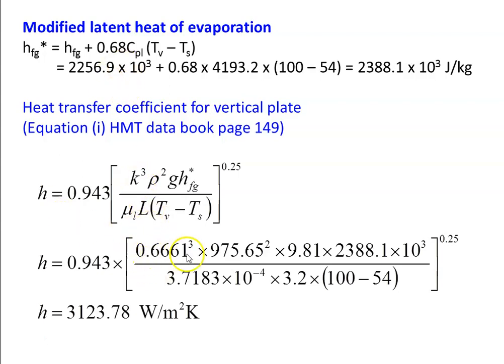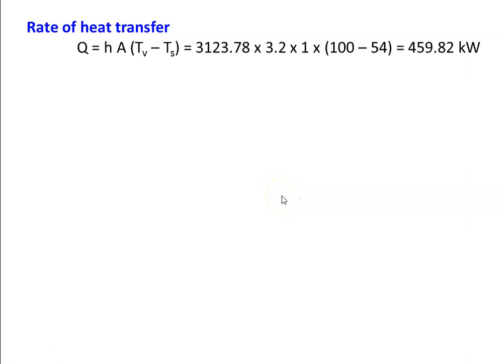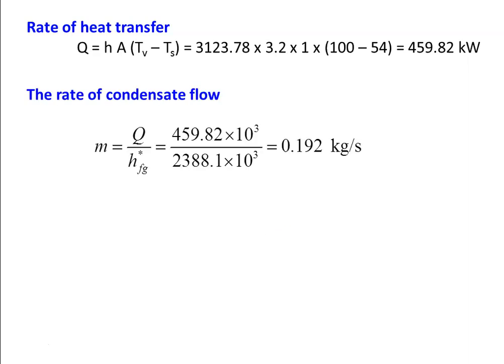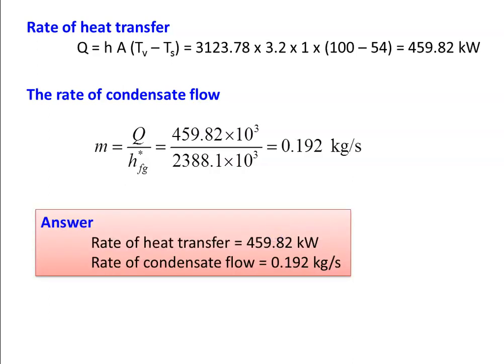Carefully check the substitution: K = 0.6661, ρ = 975.65, g = 9.81, HFG* = 2388.1 × 10³, μ = 3.7183 × 10⁻⁴, L = 3.2 m, and Tv − Ts = 100 − 54 = 46°C. The rate of heat transfer Q = H × A × (Tv − Ts) = 3123.78 × 3.2 × 1 × 46 = 459.82 kW. The rate of condensate flow M = Q / HFG* = 459.82 × 10³ / 2388.1 × 10³ = 0.192 kg/s. So the answers are: rate of heat transfer = 459.82 kW and rate of condensate flow = 0.192 kg/s.